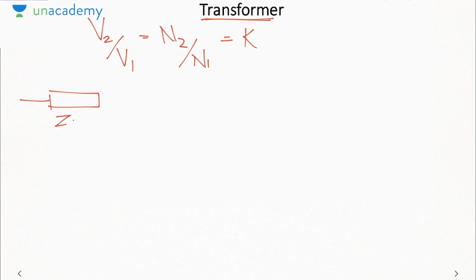Now usually we neglect the shunt parameters. Why am I neglecting shunt parameters? Because no load current in a transformer is much less compared to full load current or fault current. Fault current is even 10 to 20 times the full load current, so no load current is negligible compared to that. Hence we can neglect the shunt branch parameters, or the no load current.